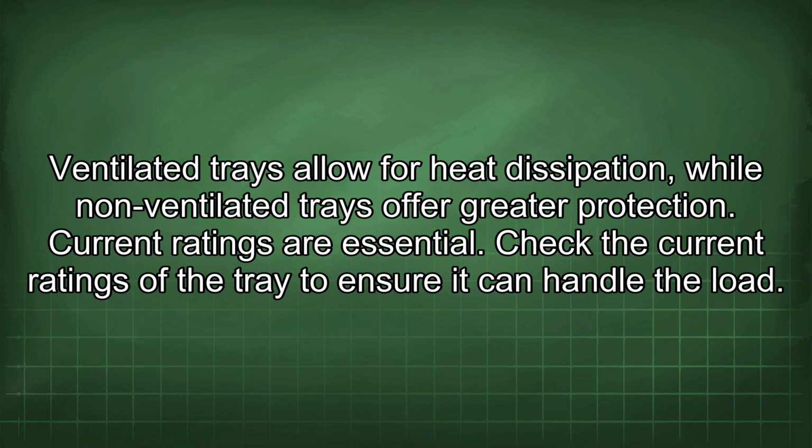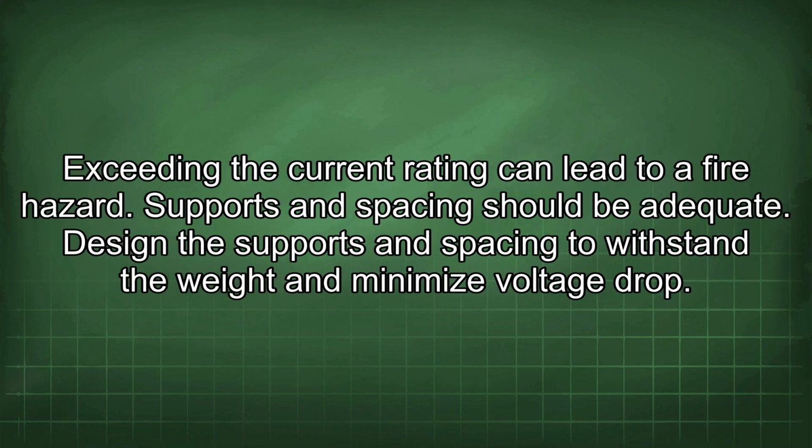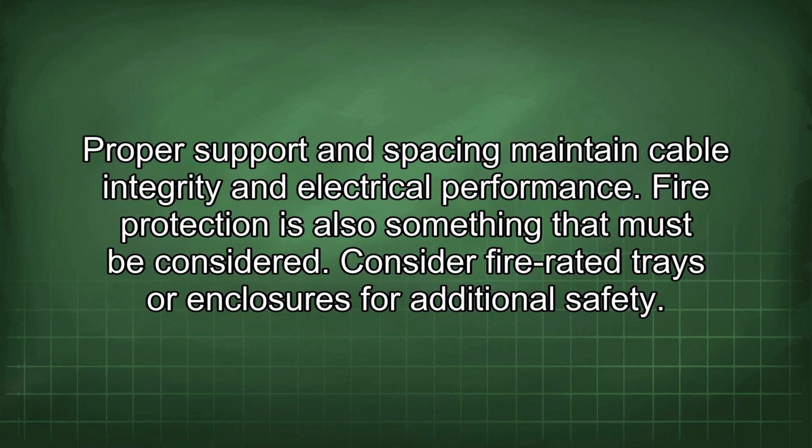Current ratings are essential. Check the current ratings of the tray to ensure it can handle the load. Exceeding the current rating can lead to a fire hazard. Supports and spacing should be adequate. Design the supports and spacing to withstand the weight and minimize voltage drop. Proper support and spacing maintain cable integrity and electrical performance.